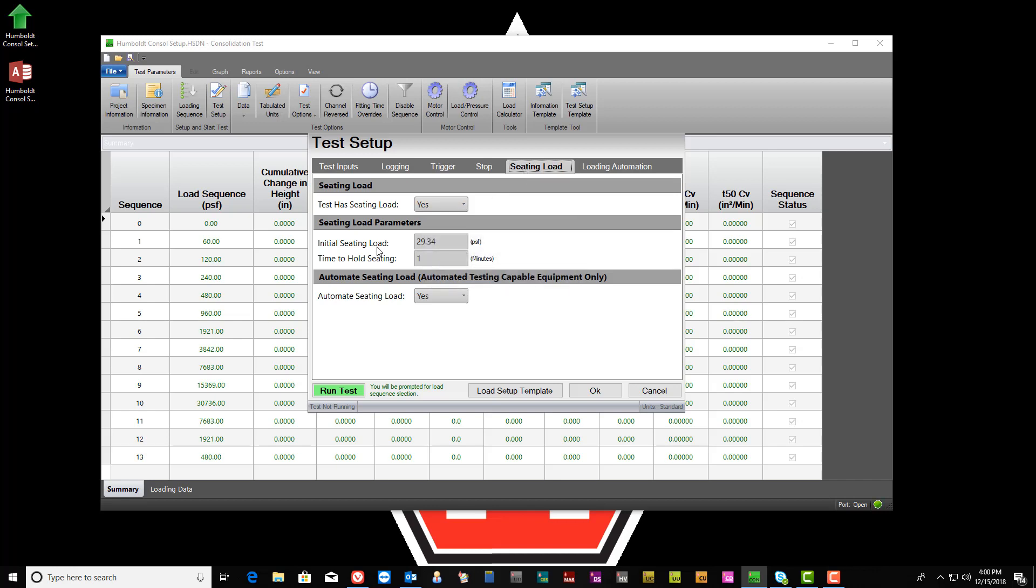There is a default seating load built into the Test Setup that includes both duration and load. However, both values can be altered to meet the tester's requirements.